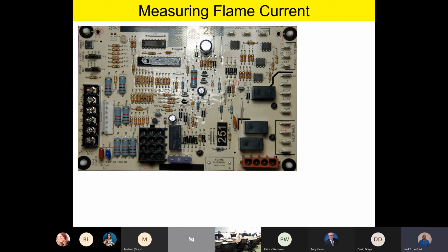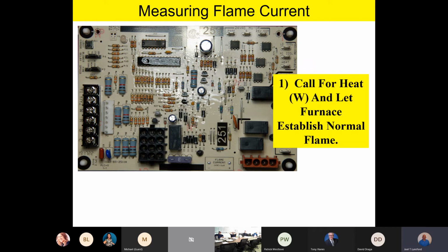So, measuring flame current, team. Here's our control board. The first thing we're going to do to measure flame current is call for heat and let the furnace establish normal flame. This is going to take about a minute or so for it to go through its normal sequence of operation. I like to let the furnace warm up a little bit and actually start blowing air into the space, just like a normal heating call.